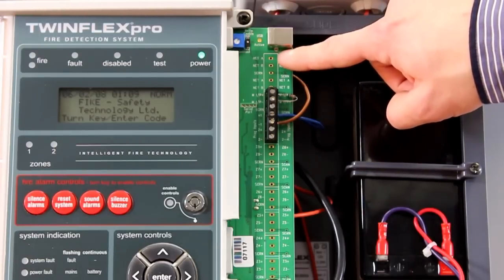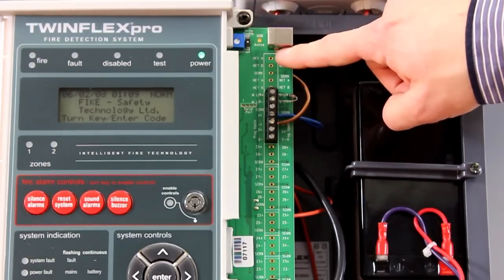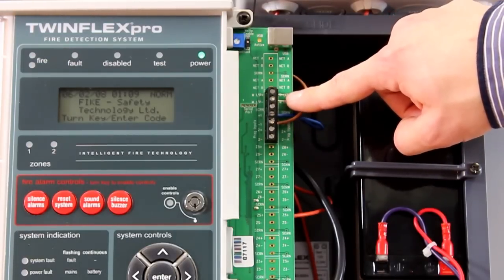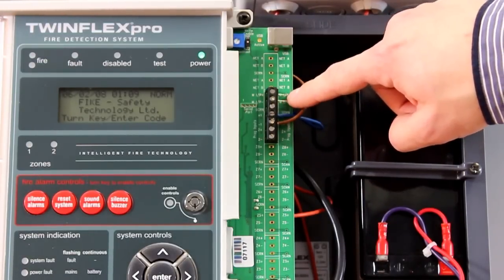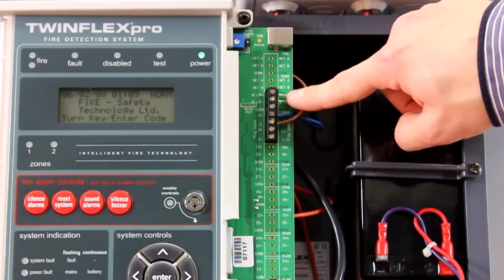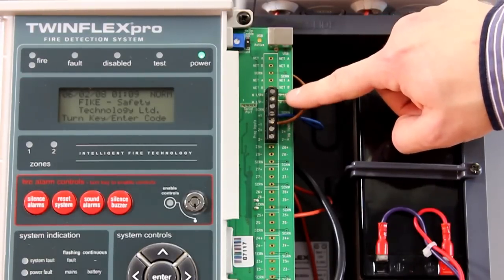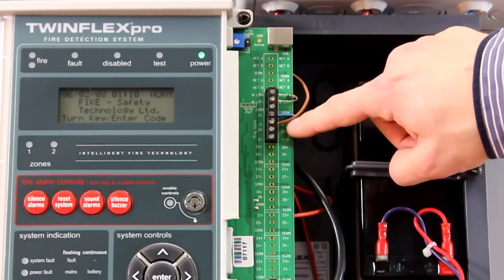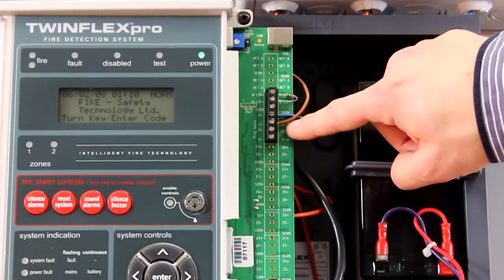Below that, on a four and eight zone, you have connect blocks for connecting your repeat panel or your mimic panels to the system. You then have a monitored input connection — its primary function is for connecting additional conventional panels onto the system and triggering vice versa. Below that you've got two unmonitored inputs which require a dry contact to activate the fire alarm panel into a condition.